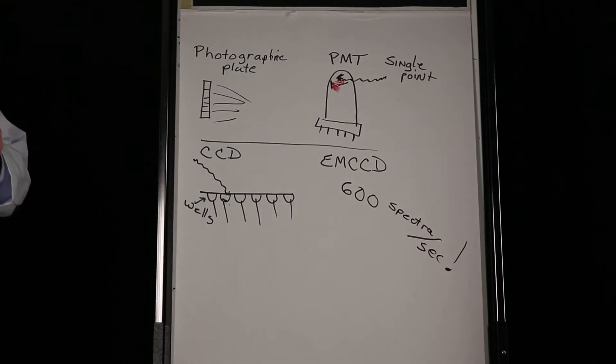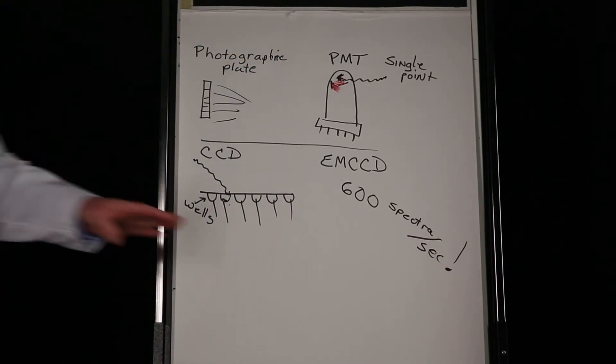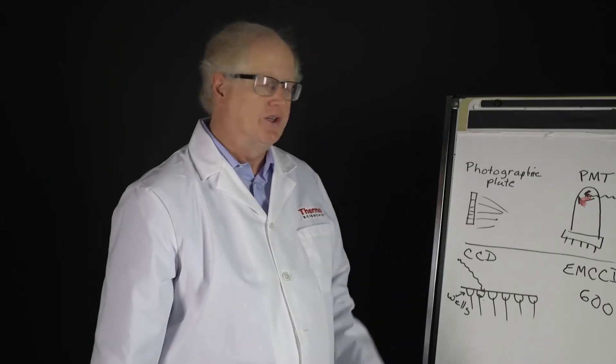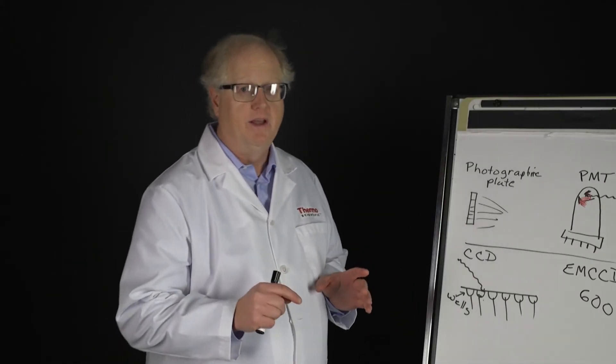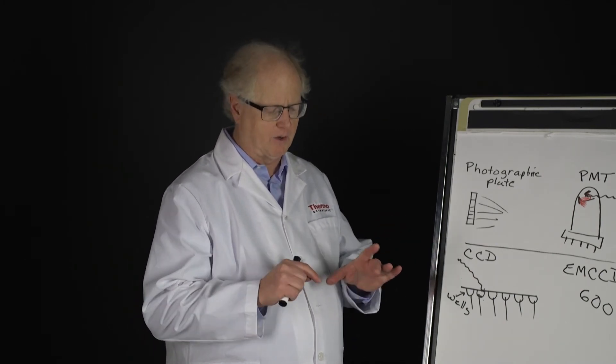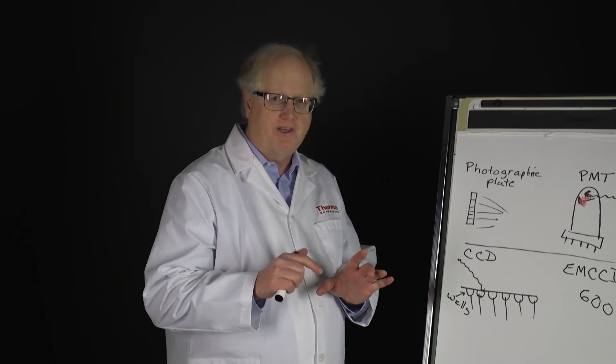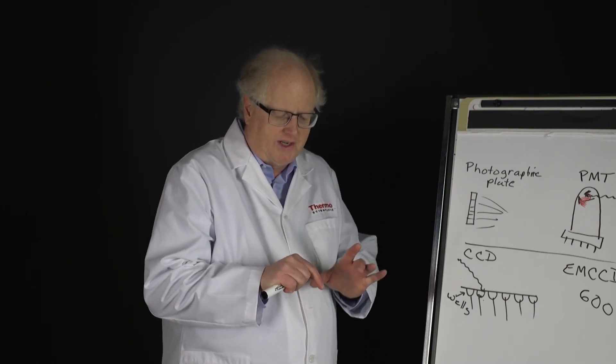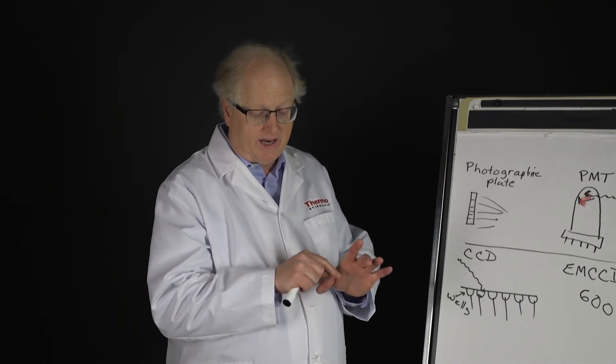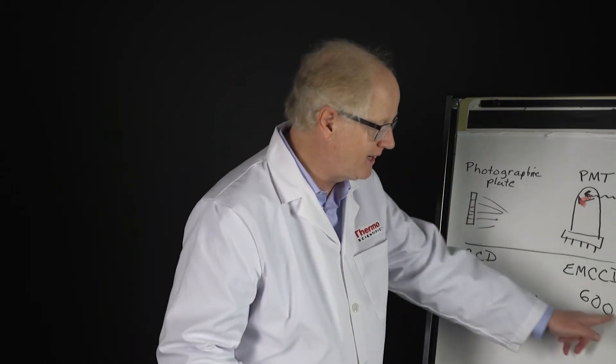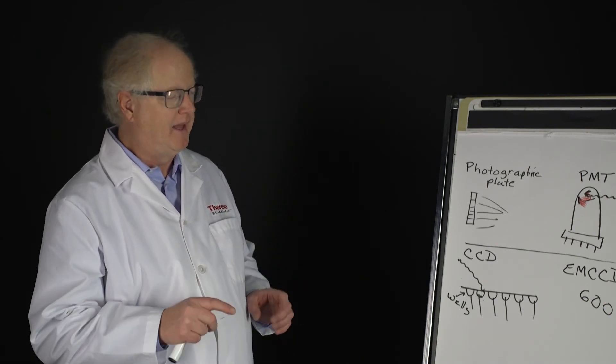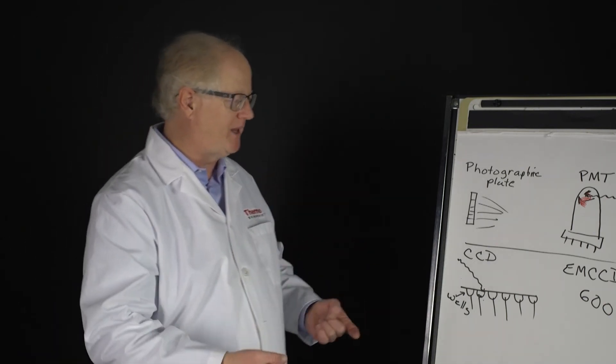That's the key for the EMCCD - it is used to allow you to collect a lot of spectra in a hurry so that you can image. And in the, again referring to the DXR Xi microscope, the stage never stops. It actually continuously scans while the EMCCD is clicking away and collecting that data, so that you can collect it at this speed, 600 spectra per second, and then co-add them to build up that image.